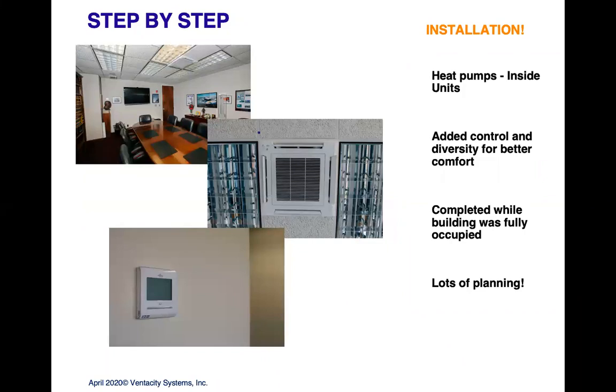And that's what it looks like inside. So again, as I mentioned, they did this while the building was occupied. They came in the evening after office hours, ran their refrigerant lines, put in the indoor units you can see there in the ceiling, ran the thermostats in the rooms. And one thing I like to point out is there's a little blue dot right here. And they really were smart. One is the contractor worked with the building owner, and they got a section of the parking garage under the building fenced off for them. And they were able to go in and, in effect, lay out the equipment before they took it up and installed it so that they could see all the different components, make sure they had everything organized so that when they went in after hours, they could get right to work and be very efficient. And that worked out really well.